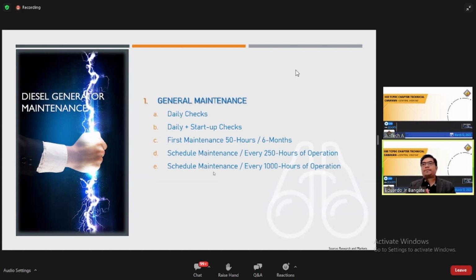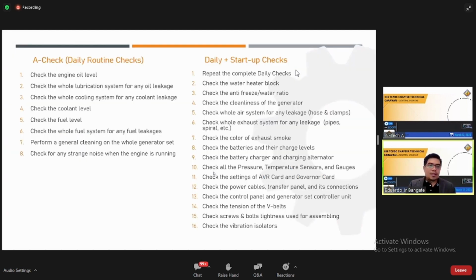Again, for those involved in generators, we always need to identify the type of operation of our generators, right? If it is prime power or standby power. Because there is a slight difference in maintenance between prime power and standby power. Normally, if it is standby power, backup power for a building, we just get a maintenance contract for it. So what is in the daily checks? It is called A-check or daily routine checks for our technicians. So what are those things that we need to check on a generator daily?